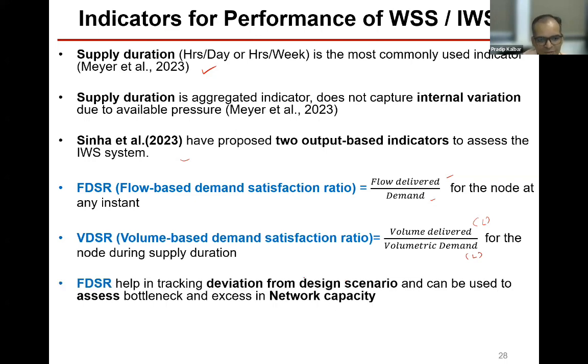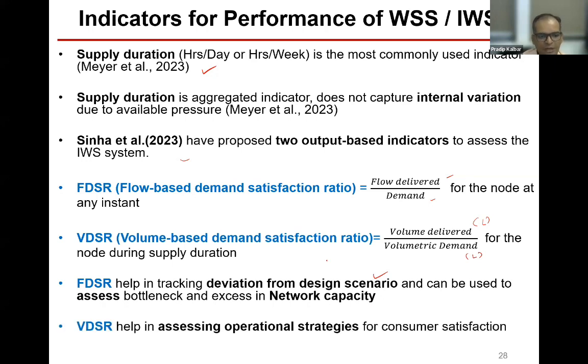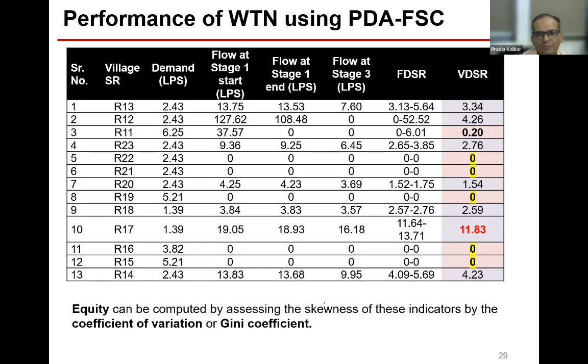FDSR helps in tracking deviation from the design scenario and can be used to assess bottlenecks and excess in network capacity. And VDSR helps in assessing operational strategies, that is, how I can control the withdrawal for different zones. Using this and using our method, we have performed the hydraulic analysis, and most of the models, if you see, will show that there is equity in the design when you analyze the initial scenario.